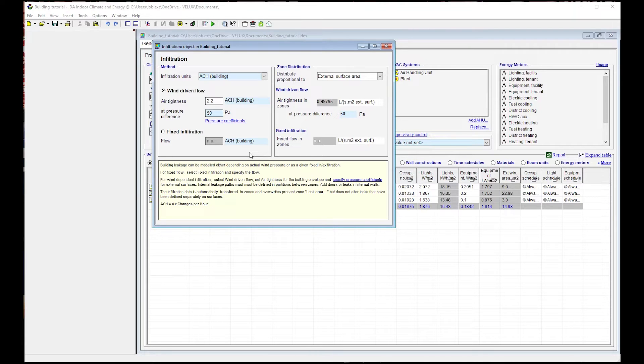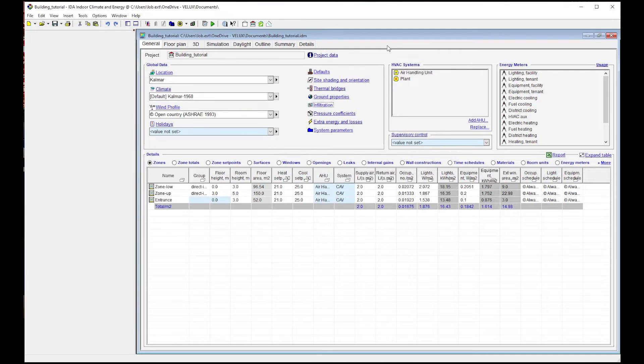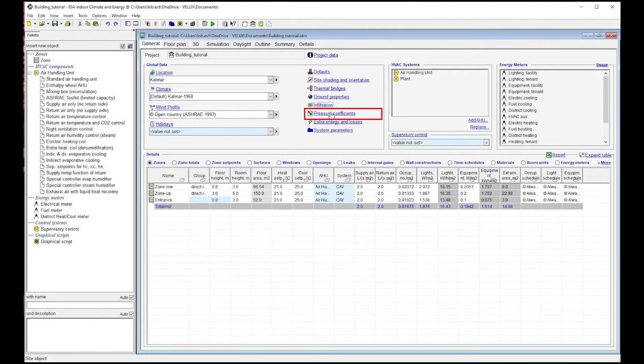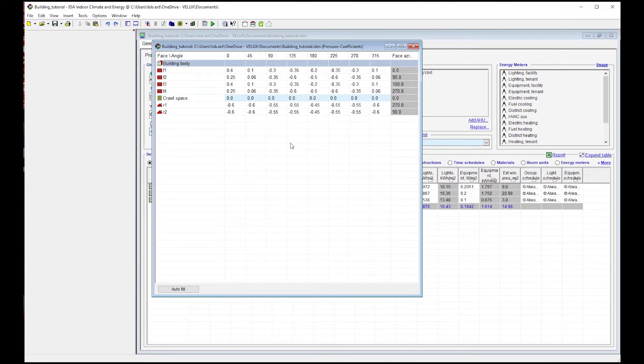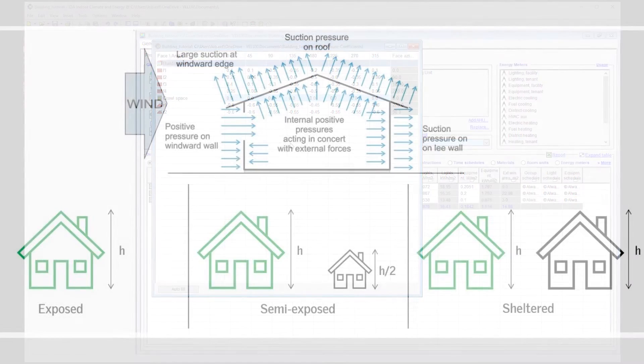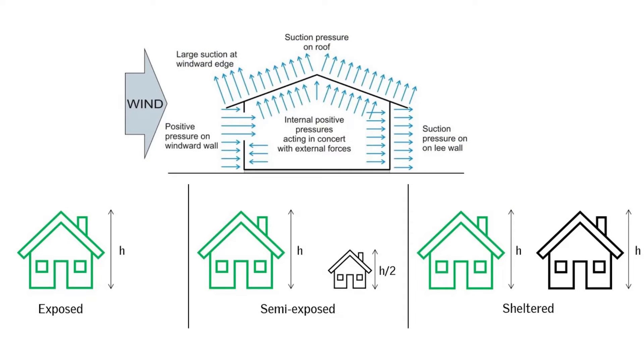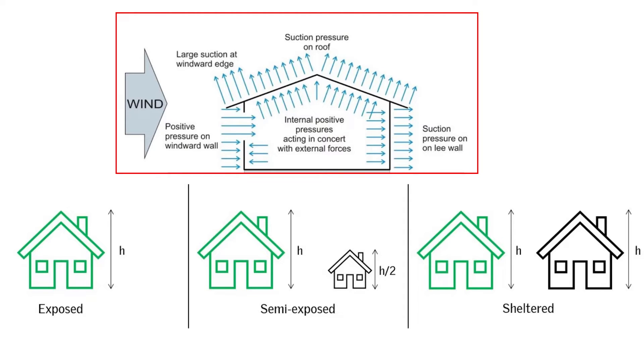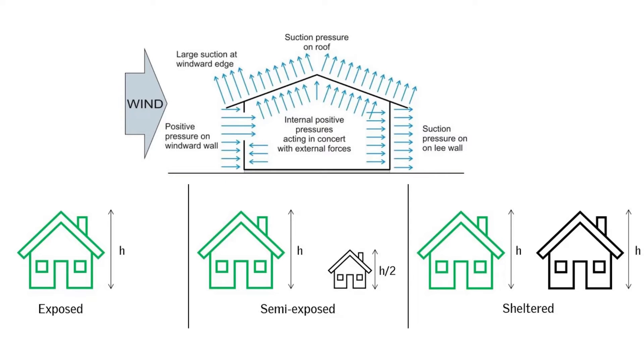After having specified the wind profile and the leakiness of the building, we need to define the pressure difference between indoors and outdoors through the immediate surroundings of the building. We will introduce the most relevant input – the pressure coefficients. Without them, the airflow through the building is not realistically calculated. When the wind blows in one direction, it causes positive pressure on the exposed wall, called the windward wall, and negative pressure on the opposite wall, the leeward wall. The pressure coefficients represent this effect, which depends on the building orientation, layout, and how exposed the building is to wind.